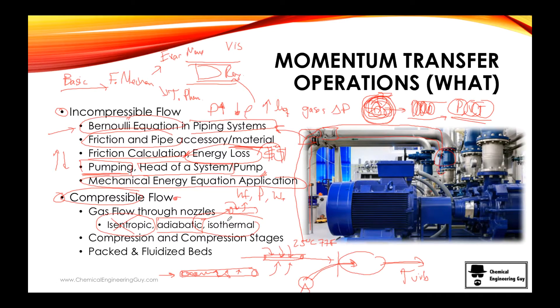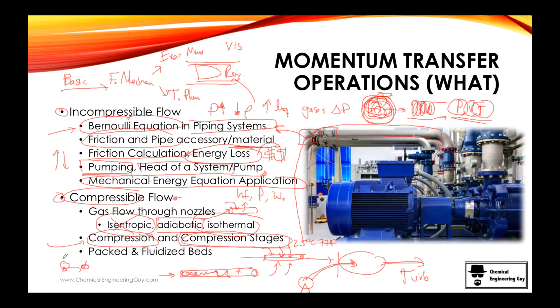Once we understand how gases move, we want to understand how to compress them. You will get to the topic of compression stages. Many times it's better to compress little by little, because if you compress all at once, you increase the temperature, meaning the next compression step requires more energy. But if you cool the gas down in between, you can compress it at the same pressure ratio with less work involved — this is the concept of compression stages.